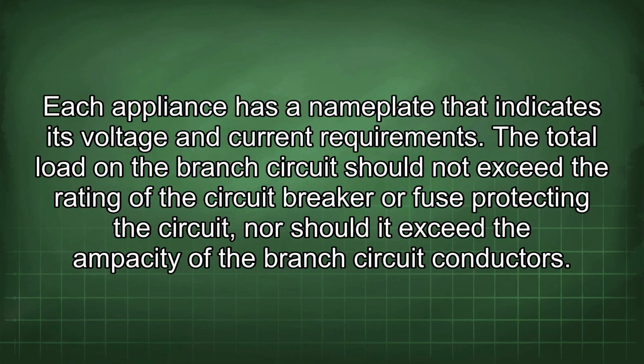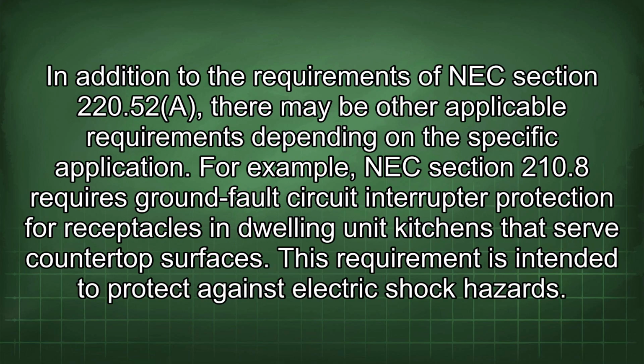The total load in the branch circuit should not exceed the rating of the circuit breaker or fuse protecting the circuit, nor should it exceed the ampacity of the branch circuit conductors. In addition to the requirements of NEC Section 220.52(A), there may be other applicable requirements depending on the specific application. For example, NEC Section 210.8 requires ground fault circuit interrupter protection for receptacles in dwelling unit kitchens that serve countertop surfaces. This requirement is intended to protect against electric shock hazards.